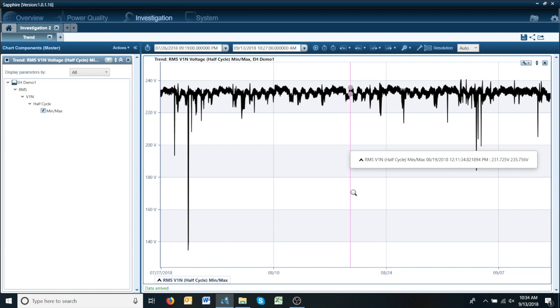One of the great powers of Sapphire is it has the ability to create these graphs instantly. So what we have here is we have a trend plot from a couple months worth of data and as you can see there are some SAG events.